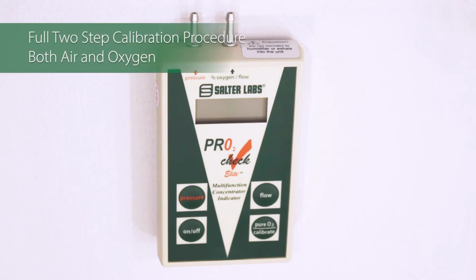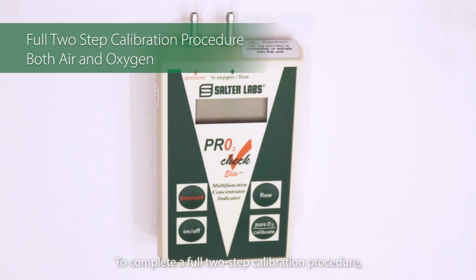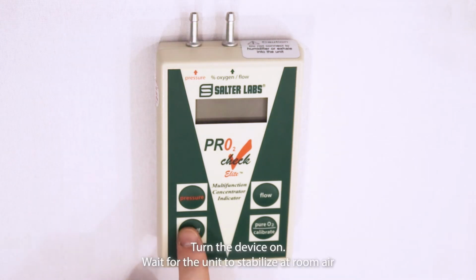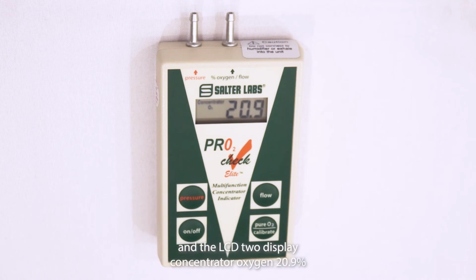required. To complete a full two-step calibration procedure, do not connect the device to an oxygen source or introduce oxygen to the unit. Turn the device on. Wait for the unit to stabilize at room air and the LCD to display concentrator oxygen 20.9%. If concentration is higher than 22%, airflow can be used to purge the chamber, or a syringe can be used to provide a slight suction. Do not exhale or breathe into the device. When the reading is stabilized, turn the device off.